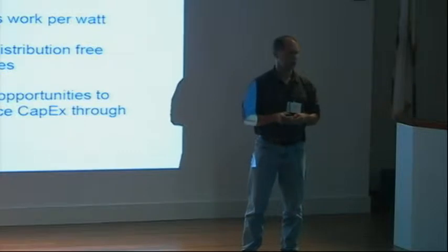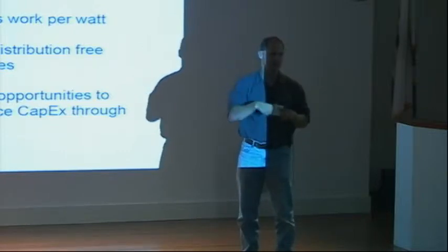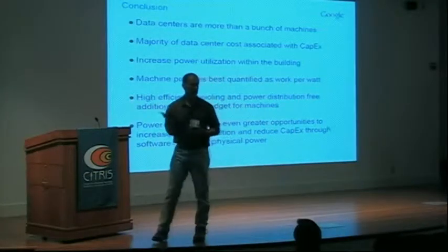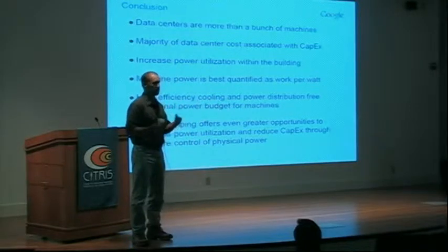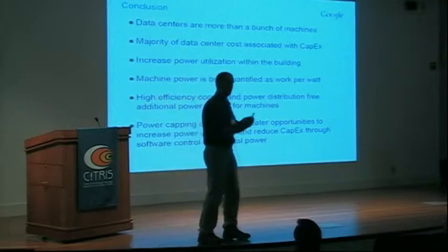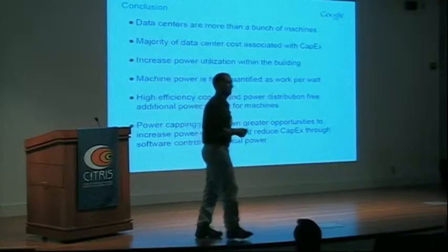Right now, for example, our data centers run somewhere between 1.12 and 1.2 power utilization efficiency, which means for every watt that gets to the server, 1.12 watts comes in from the street, and that accounts for all energy conversions and all the cooling. So it's a 12% overhead, and that's our officially released numbers that we make as high as possible so that no one can yell at us. But we have other numbers internally that usually point to them being possibly a little bit better than that, but not official.